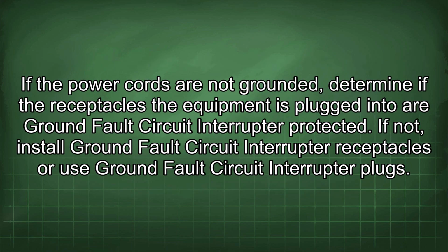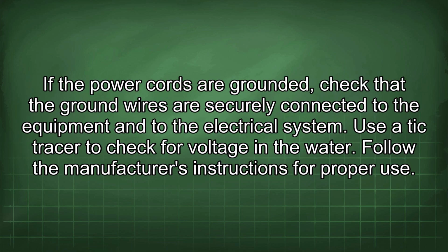If the power cords are not grounded, determine if the receptacles the equipment is plugged into are ground fault circuit interrupter protected. If not, install ground fault circuit interrupter receptacles or use ground fault circuit interrupter plugs. If the power cords are grounded, check that the ground wires are securely connected to the equipment and to the electrical system. Use a tick tracer to check for voltage in the water. Follow the manufacturer's instructions for proper use.